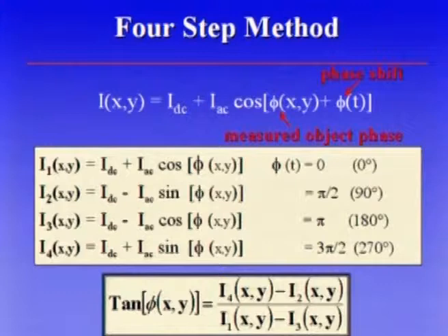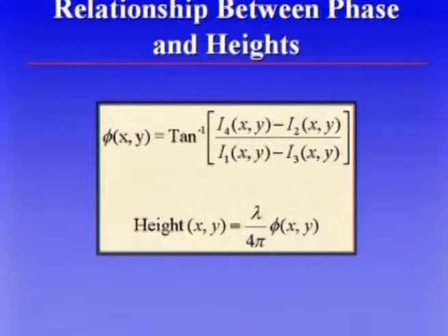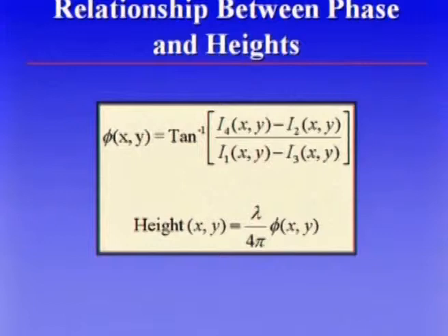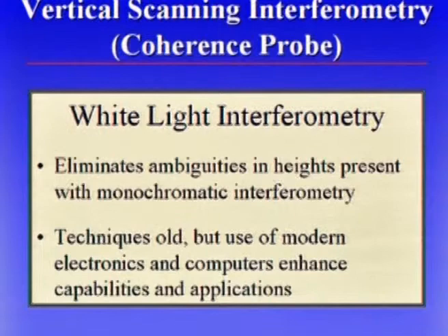So the phase calculated is the arc tangent of that ratio. Looking at normal incidence, I take whatever I calculate, divide by 4π, multiply by the wavelength, and get the height variations across the sample. It's a very powerful, simple equation that has become more powerful as computers, detector arrays, and electronics have improved. The limitation of this technique is you can't measure very large steps or very rough surfaces. That takes us to our second mode of measurement: the vertical scanning or coherence probe technique. These techniques are not new, but with modern electronics and computers they have become very powerful.